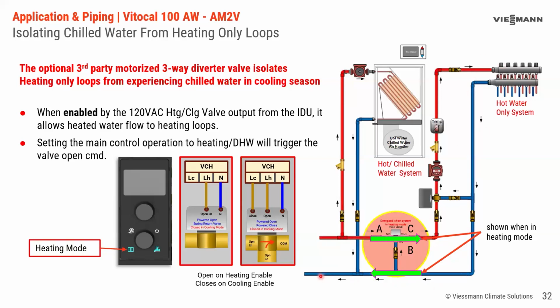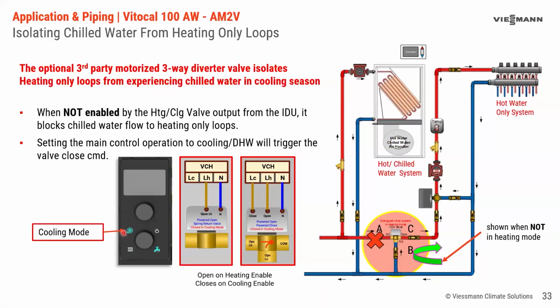Now, when the system is in cooling, okay, so we have the cooling and domestic hot water function. This valve is unpowered, the spring return valve, and this valve is powered on the cooling side, which blocks flow this way and allows chilled water to go this way.